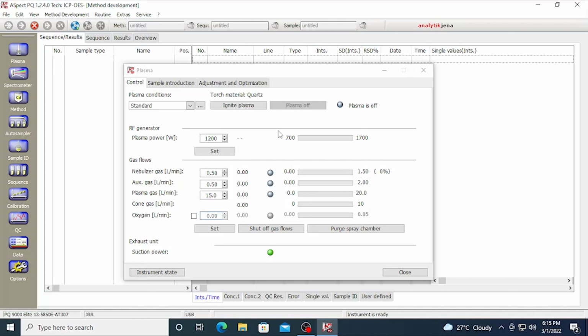So ako, since I've already done purging the optical bench, I can now start conditioning my plasma. So what you need to do is set the gas flow. By the way, I already started using my fume hood, my exhaust. So don't forget to turn on your exhaust as well as to put your samples on the auto sampler. So samples are already in there, just waiting to be analyzed. If this green indicator is already turned green, that means your flow rates are already set. So I can now start purging the spray chamber.